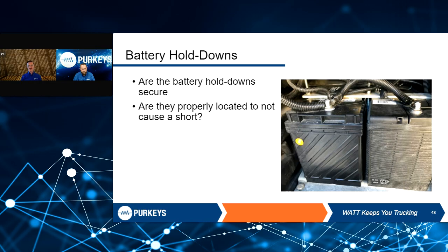We mentioned earlier, making sure everything is tight inside of that battery box. Battery hold downs get a little tricky because Jimmy and I, being out in the field, have seen a number of battery hold downs completely loose. Huge issue there. If it's loose enough where that hold down bracket can slide back and forth, and you hit one of those positive studs, it's going to throw a lot of sparks and it's not going to stop. But we've also seen it where that battery hold down is over tightened, squashing the tops of the batteries. You don't want to put that much pressure on these batteries. You should not be tightening these down with power tools. Get it nice and tight with your 3/8 ratchet, by hand. Just make sure you're not over torquing or under torquing them.